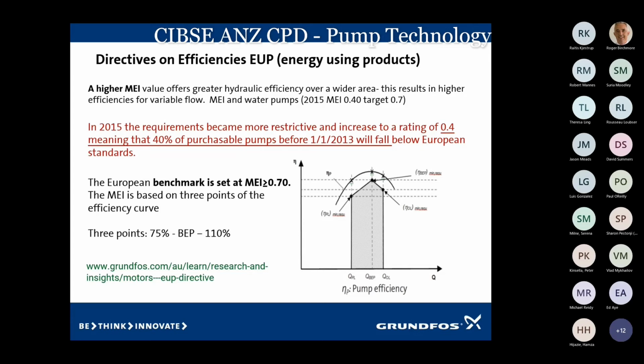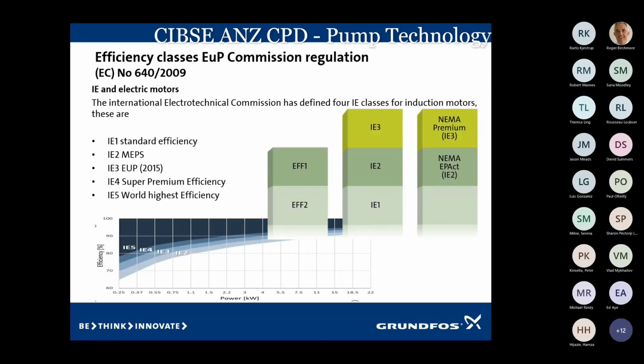The bulk of our systems now are variable loads that we don't generally run as a fixed speed or on a 3-port valve. Motor efficiencies, the EuP directive for motors for some time now has been IE3. We have an efficiency standard here, efficiency 1, efficiency 2. Looking at the European one, they have an IE standard, and efficiency 1 is equal to their IE2, whereas their standard minimum motor requirements are IE3. Motors now, we have out with IE5 motors. An IE5 motor is 10% more efficient than an IE3. Energy savings are just quite huge.